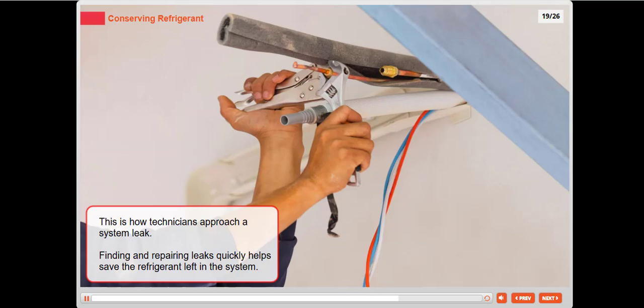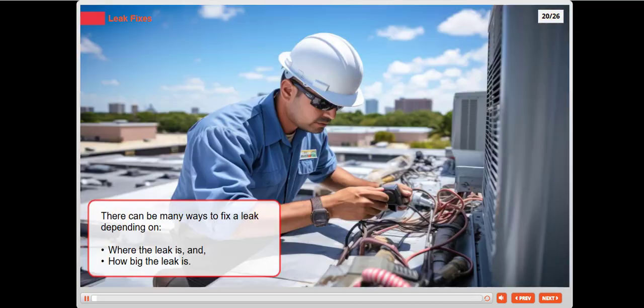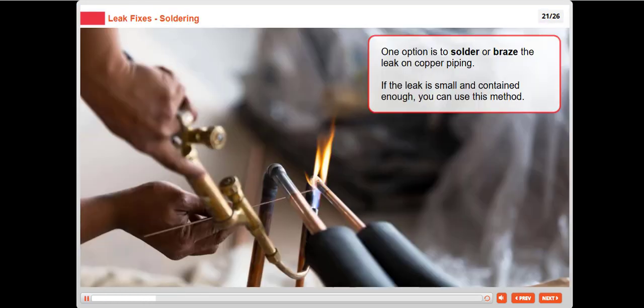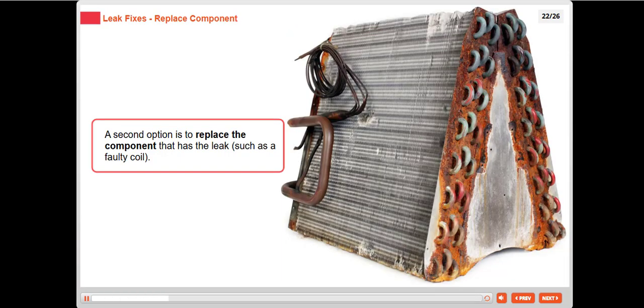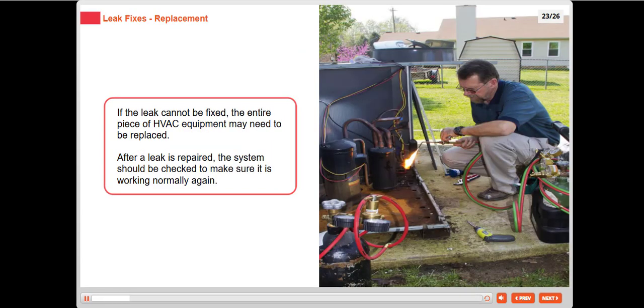There can be many ways to fix a leak depending on where the leak is and how big the leak is. One option is to solder or braze the leak on copper piping. If the leak is small and contained enough, you can use this method. A second option is to replace the component that has the leak, such as a faulty coil. If the leak cannot be fixed, the entire piece of HVAC equipment may need to be replaced. After a leak is repaired, the system should be checked to make sure it is working normally again.